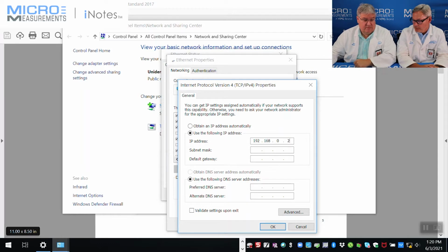One of the reasons we pick something other than 1 is that a lot of times if you're going to connect the 8000 into a router, that router will have a default IP address of 1. So typically we skip over 1. We of course can't have the same IP address as the 8000 scanner, which is 4.